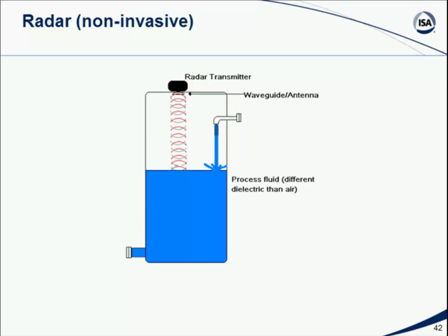Radar technology can be non-invasive in some cases. And what do we mean by that? Well, if we have a tank that is invisible or transparent, shall we say, to radar, for example, the tank is not metallic, it's made out of plastic or something, then we can mount our radar transmitter outside the tank and never have to be inside the tank at all. On the other hand, if we have a metal tank, we can sometimes mount a porthole in the top of the tank, something that has a very strong glass or some other type of transparent material, again, something that radar doesn't really see and can go through, so we can still keep the radar transmitter outside the tank. So if we're dealing with caustic materials or something where we really just don't want to put a penetration into the tank because of tank pressure, for example, then sometimes we can use a non-invasive radar transmitter.